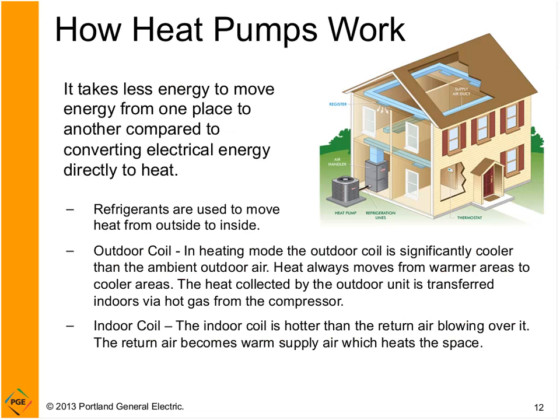Refrigerants are used to move the heat from outside to inside during heating mode. There's an outdoor coil or an outdoor unit. In the heating mode, the outdoor coil is significantly cooler than the ambient outdoor air. Heat always moves from warmer areas to cooler areas, the laws of thermodynamics. The heat is going to be drawn from the outdoor air to that coil. The heat is collected by the outdoor unit and transferred indoors with a hot gas refrigerant from the compressor. And then there's the indoor coil, and the indoor coil is hotter than the return air blowing over it, which results in warm supply air and heats the space. And this is just a diagram here of a typical single-family home with a ducted heating system, a heat pump.